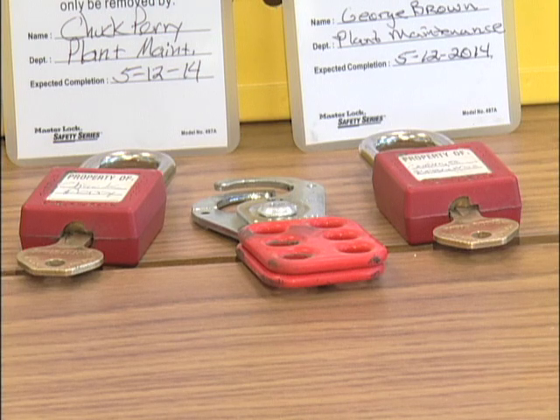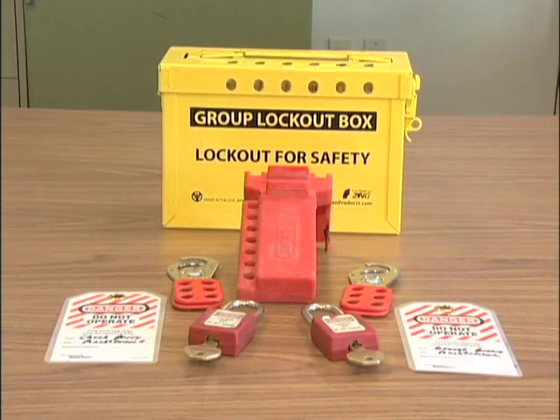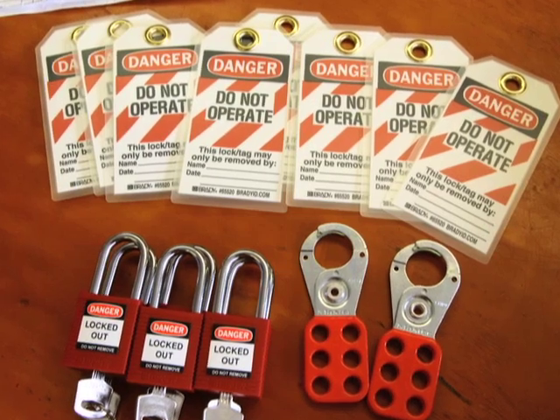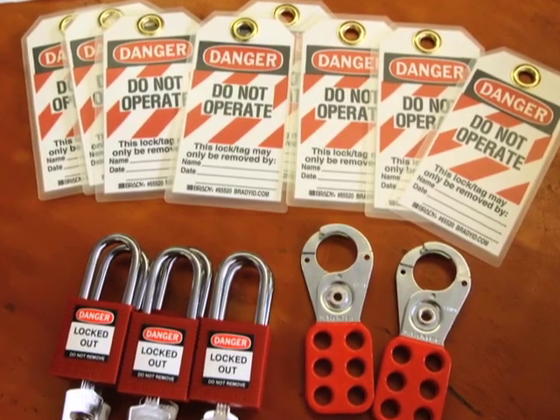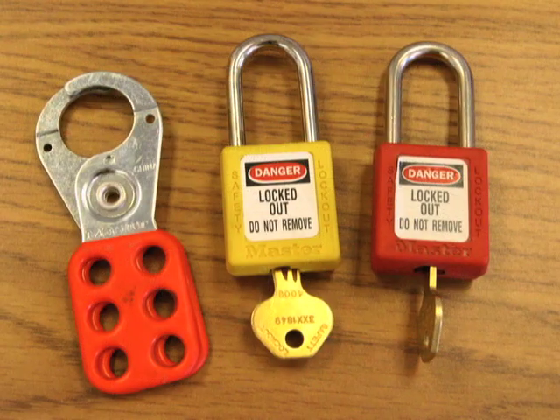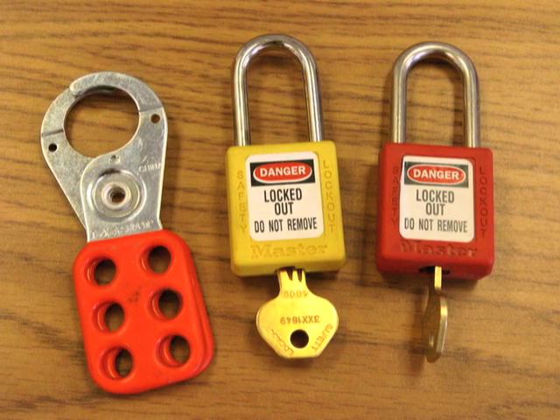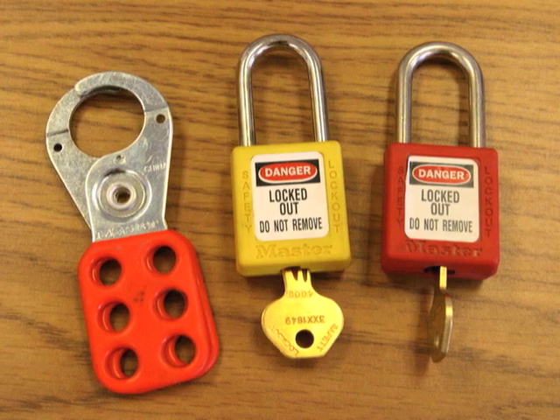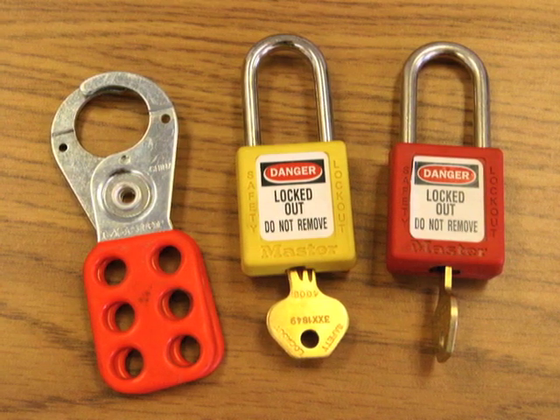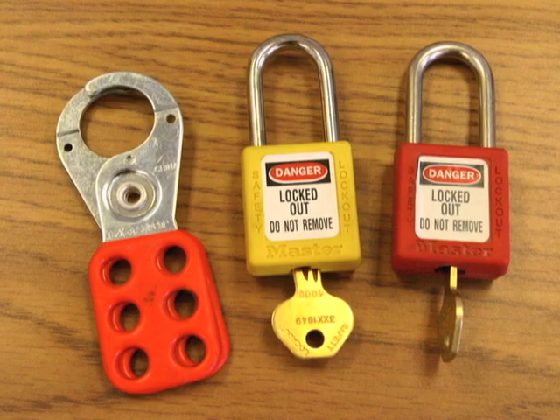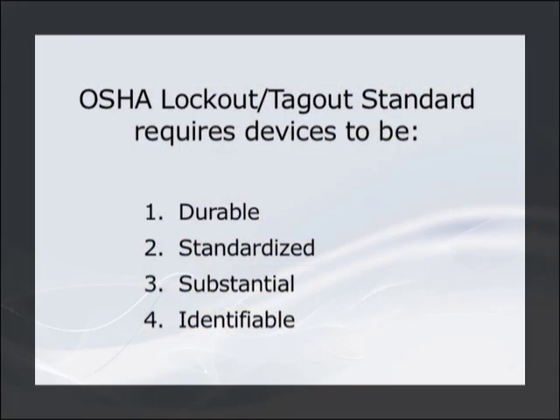These devices are going to come in all shapes and sizes to fit and to lock out and tag out equipment and machinery using different sources of hazardous energy. The devices must have a standardized look, color, and shape. A standardized color scheme would be red devices for plant employees and yellow devices for contractors. The OSHA Lockout Tagout standard specifies that devices must be 1. Durable, 2. Standardized, 3. Substantial, and 4. Identifiable.